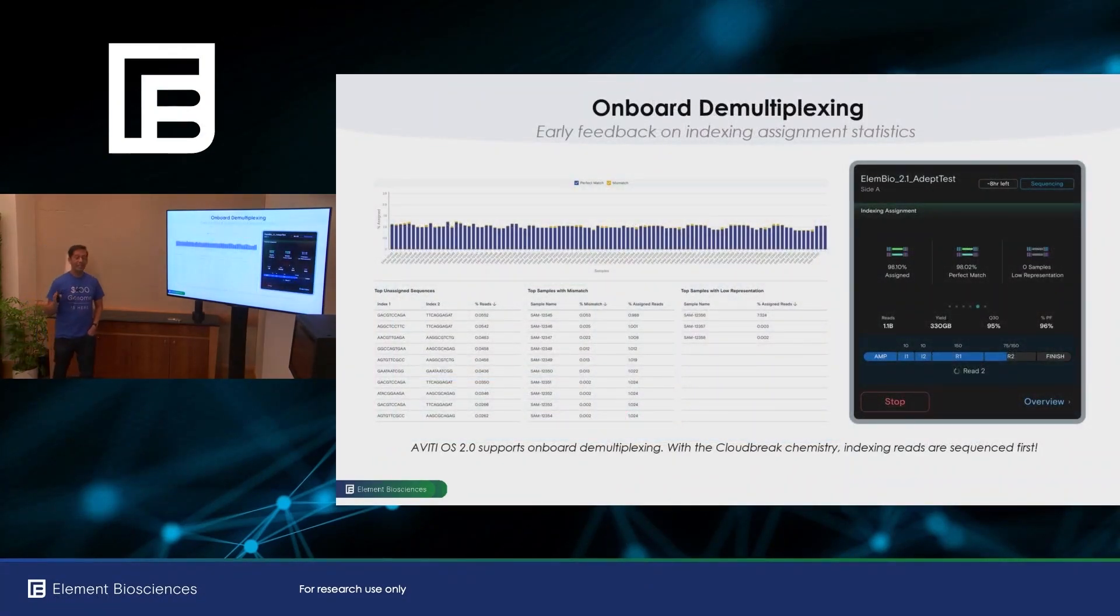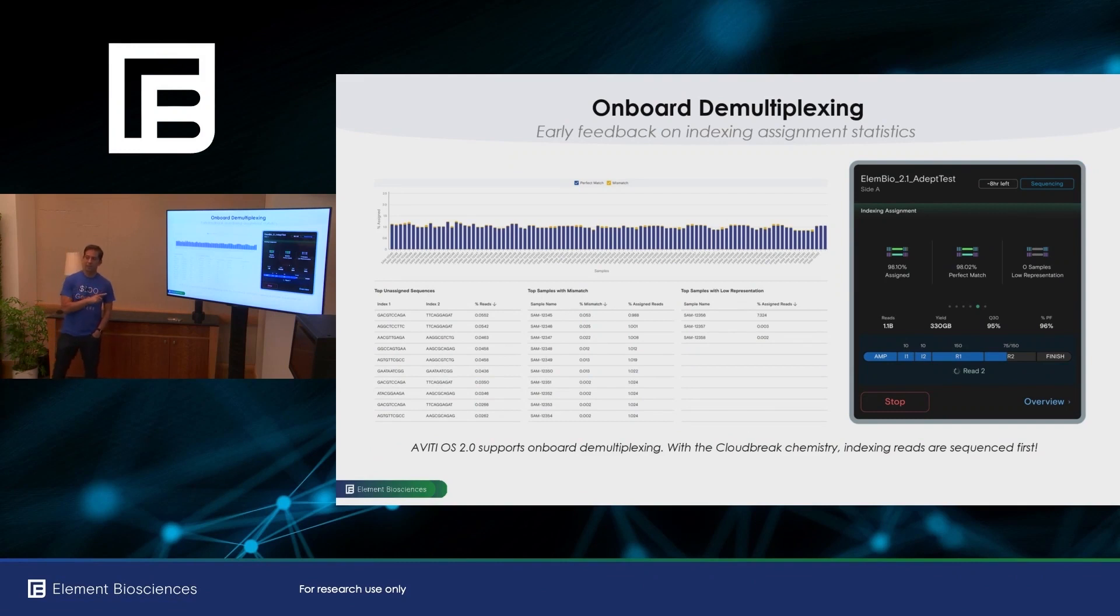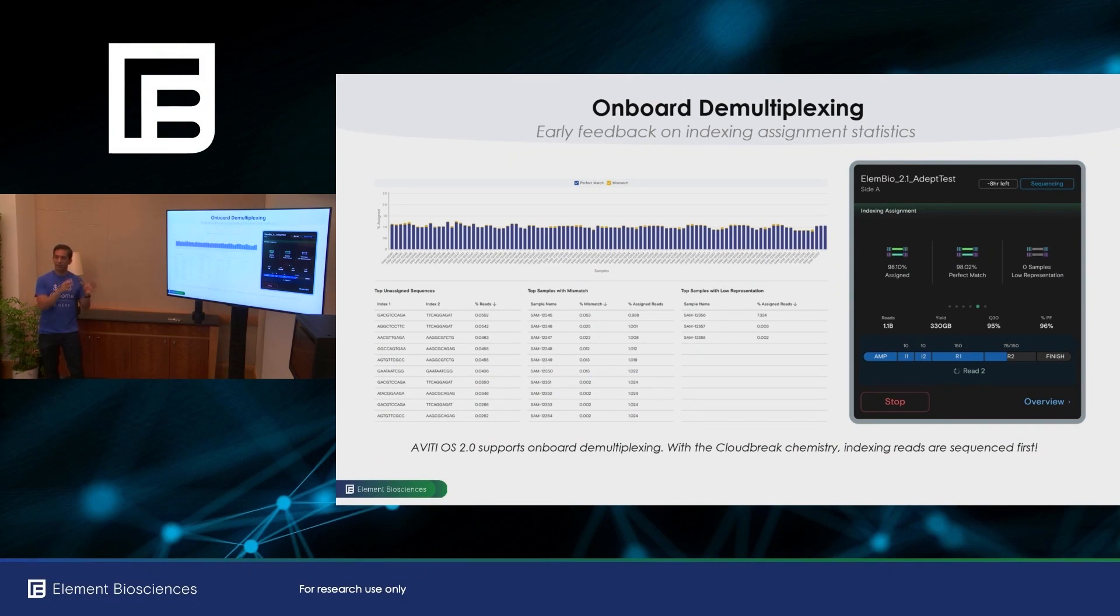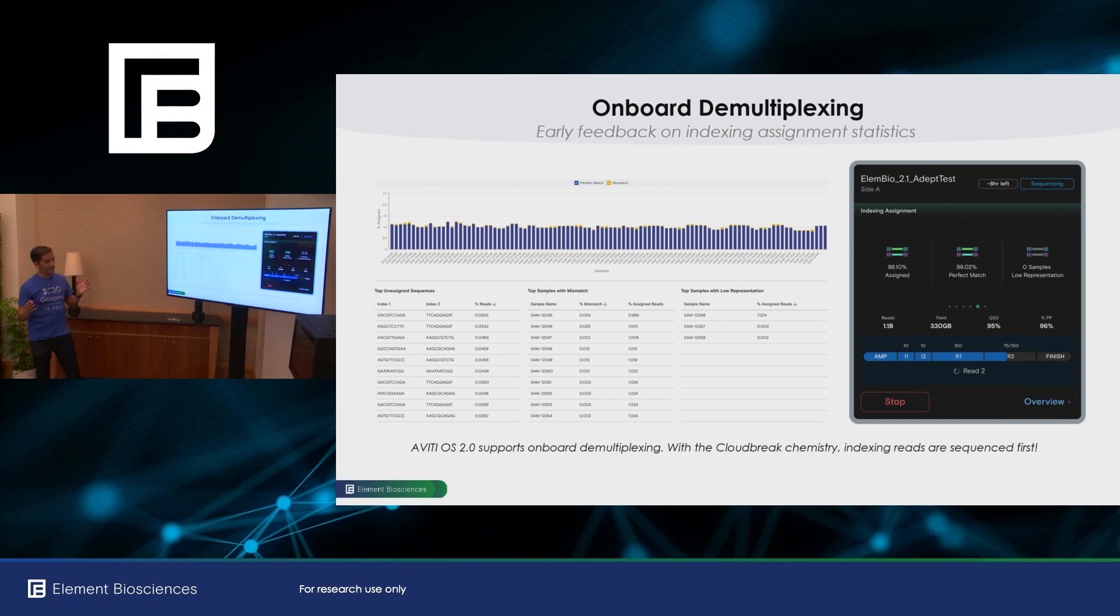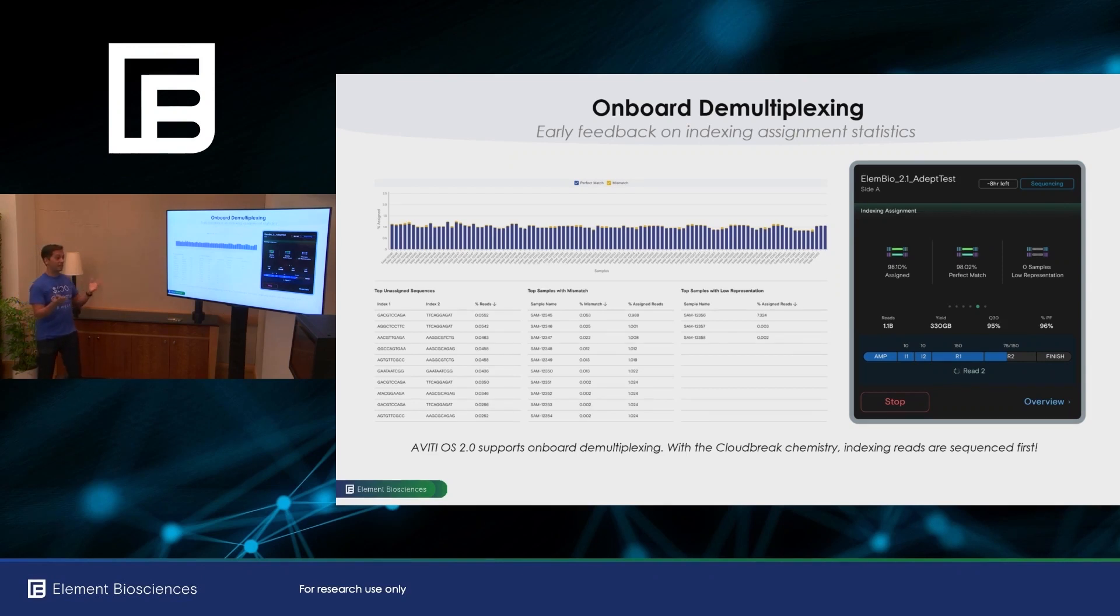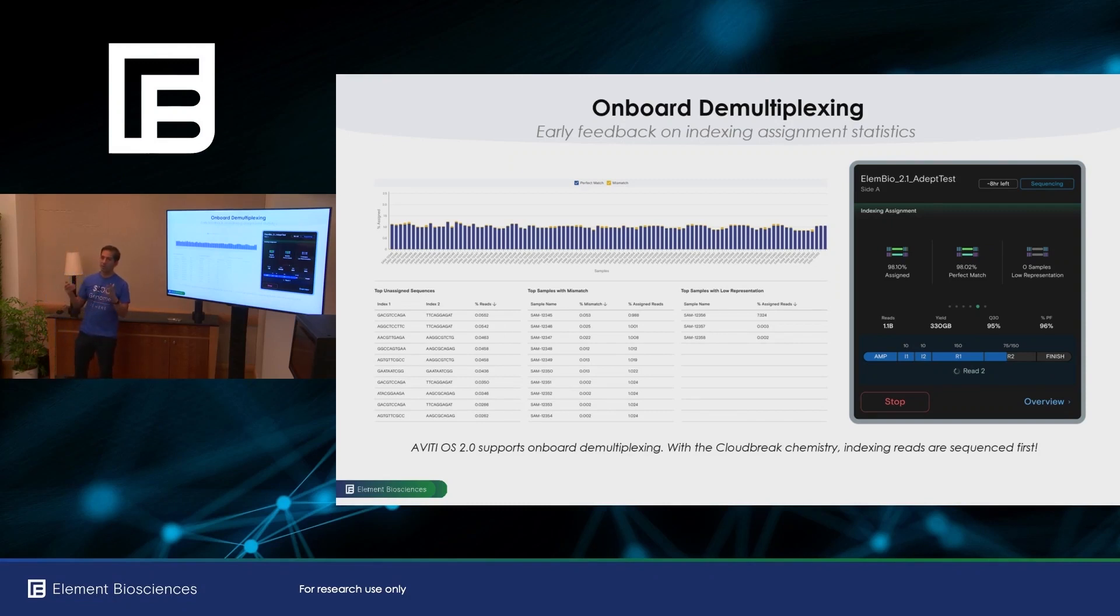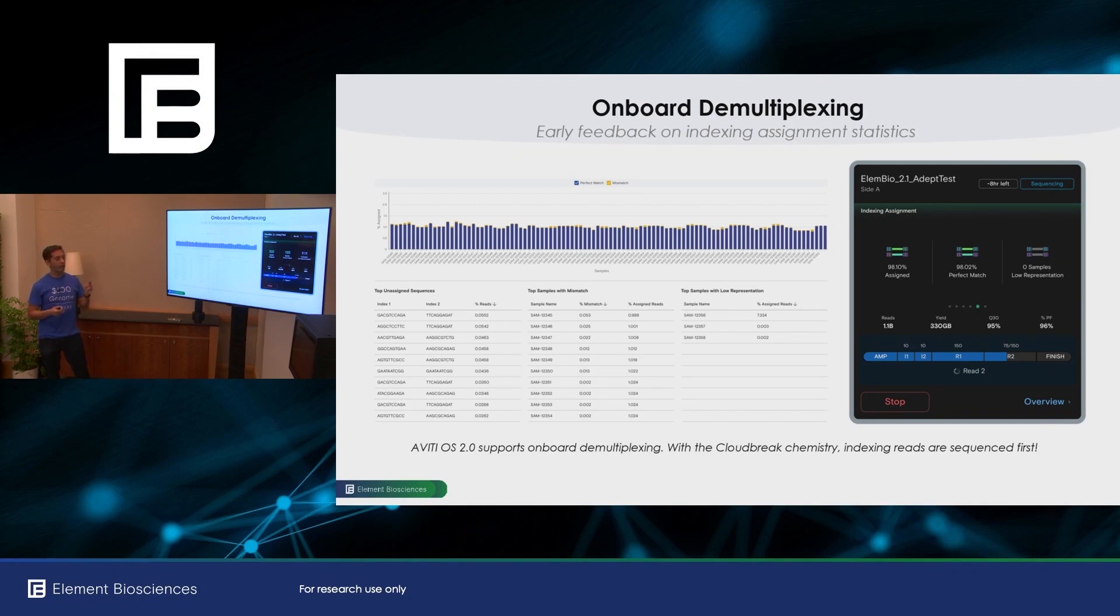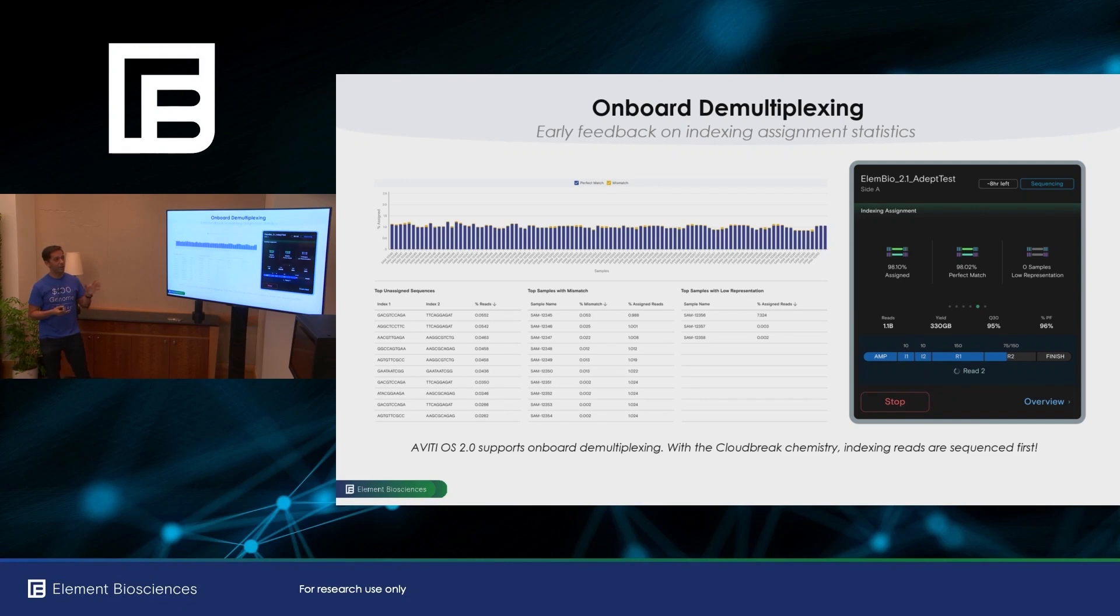So one of the really exciting new features in Aviti OS 2.0 is this ability to do onboard demultiplexing. Again, demultiplexing is the association of which data go with which samples. And so as a result, you get indexing statistics. On the instrument, you'll get overall summary statistics. But also with Cloudbreak, and this is really very exciting, in my opinion, is that we're moving the index reads to come first. So you'll get these data very early in your run. If there's any sort of manifest issues you'll be identifying those, those can be corrected after the fact. But if there's a library issue, then you can stop the run and save valuable sequencing time.